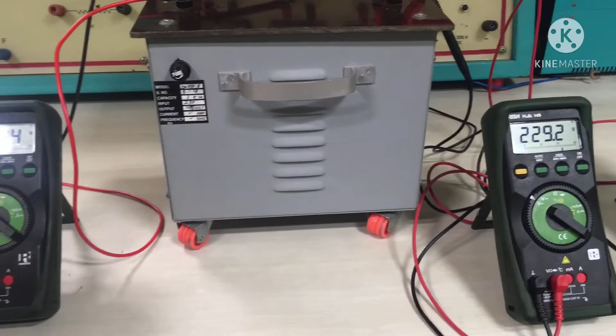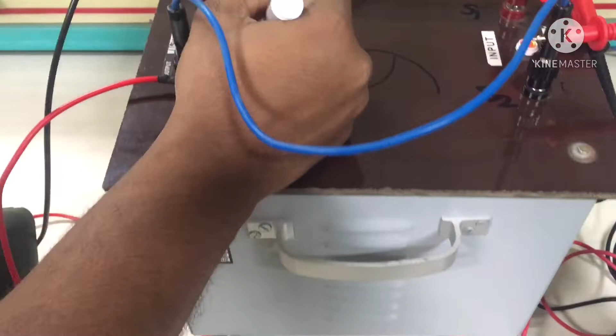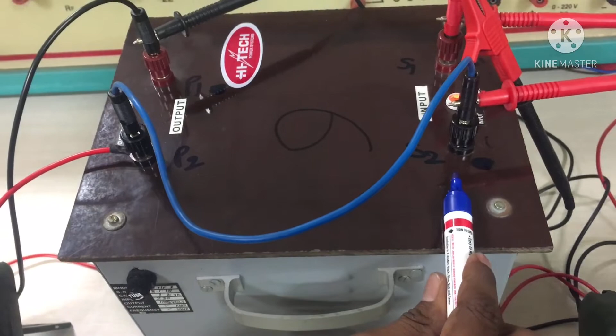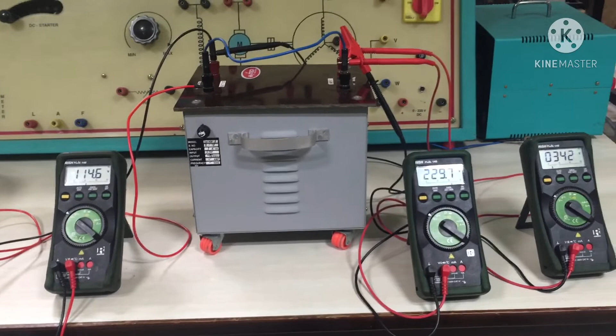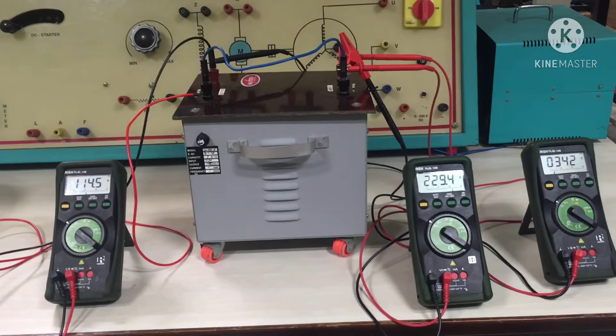Therefore, the dotted polarities should be the P1 and S2 terminals. So here P1 is the dot polarity and S2 is the dot polarity here. We have marked the dot polarity for the primary winding and we have marked the dot polarity for the secondary winding. Polarity test is one of the necessary tests for connecting two or more transformers in parallel. We have marked the polarities of primary and secondary windings for the given transformer.